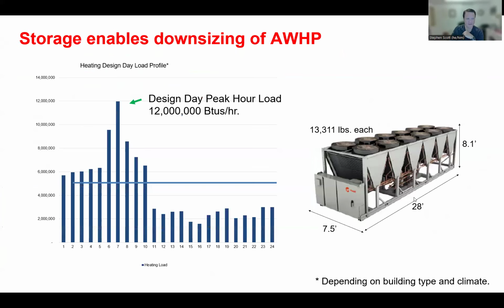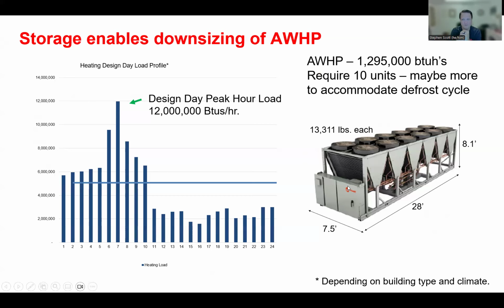The next slide gives a little bit of a graphic of a heating design day, and say you had to size it for your heating design day of 12 million BTUs per hour. If you just do it solely with air source heat pumps, in this example, you need about 10 of them on the roof. You just hit click once to go forward. There we go. Maybe more to accommodate defrost depending on your building type.